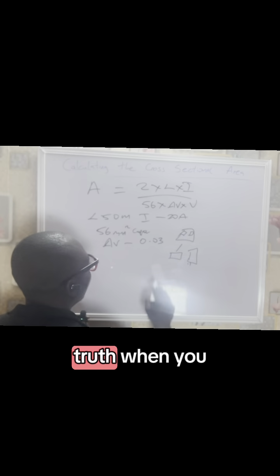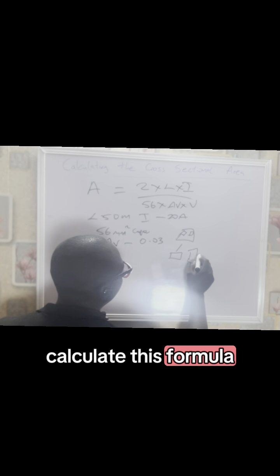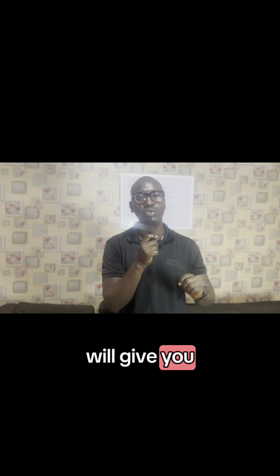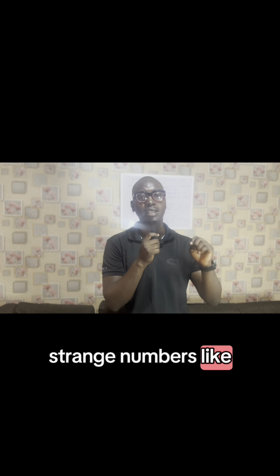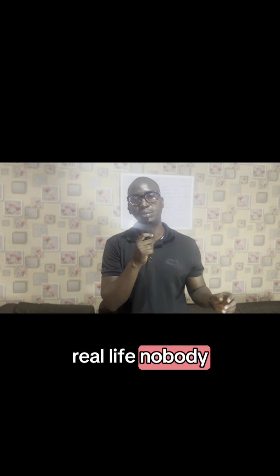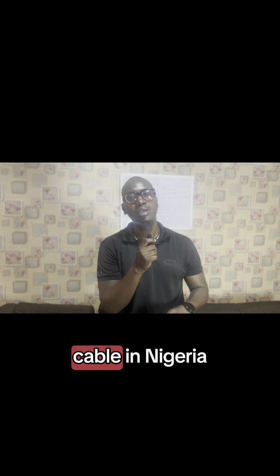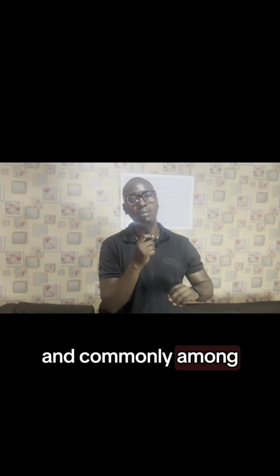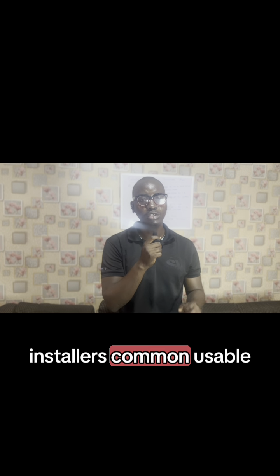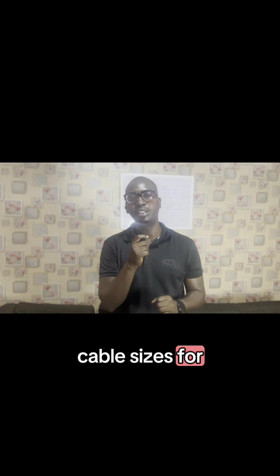Now, here's the truth. When you calculate this formula, sometimes the answer will give you strange numbers like 3.2 mm² or 7.4 mm². But in real life, nobody buys 3.2 mm cable. In Nigeria and commonly among installers, the common usable cable sizes for DC connections are 2.5 mm², 4 mm², 6 mm², and 10 mm².